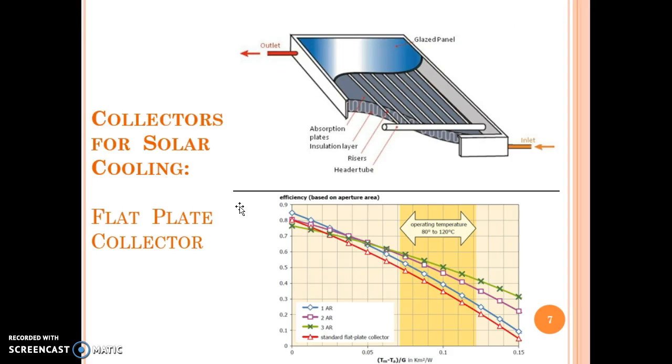The collectors for solar cooling: one of the collectors is explained here, which is a flat plate collector. These are the typical components of a flat plate collector. You have glazed panel or the glass cover at top. You have two headers—this is the header tube at the bottom from which the cold water enters, and you have outlet from here where the hot water comes out. You have the tubes connecting the two headers, and these tubes are in good thermal contact with the absorber plate.